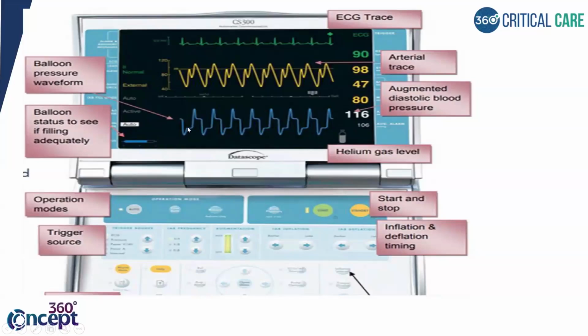Next is your balloon pressure waveform. So how is the balloon getting inflated? This is how the balloon waveform looks. Next is the operative mode, whether it is auto mode or which mode. Next we have the trigger options, the IABP frequency, and the augmentation level. We have the positioning of the inflation and deflation, whether you should make the inflation early or delay it, or make deflation early or late. So this is for the timing of the inflation and deflation. And we have a standby switch and a start and stop switch.